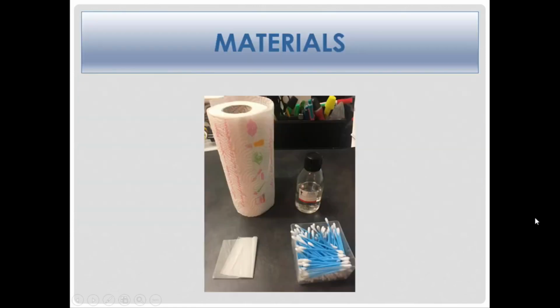Even for immersion oil lenses, when the oil dries, it changes the refraction of light and will affect the quality of your image. You need to clean the encrusted oil off the lenses regularly. You could just use pure alcohol for cleaning lenses, but I prefer to use this mixture of 70% alcohol and ether. I obtain the mixture at the pharmacy, but if you struggle to obtain it wherever you are, ask your microscope supplier for help. This mixture of alcohol and ether dries more rapidly and dissolves the oil more effectively than alcohol alone.